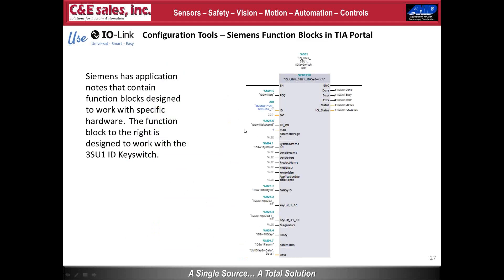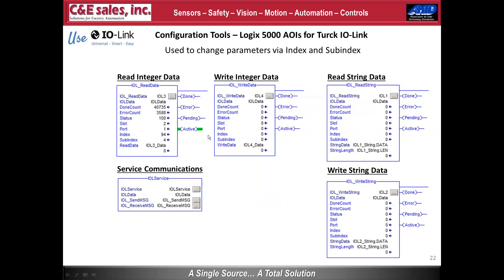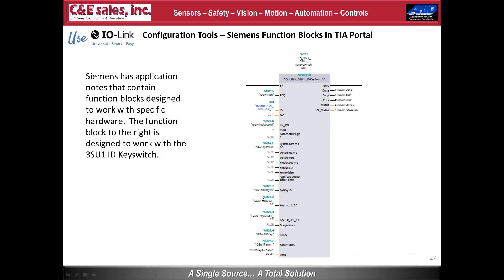Here's an example of the Siemens IO-Link device block interfacing with a Siemens Sirius ID key switch. The ID key switch uses keys with unique hex codes and authorization levels for machine or HMI access. Using the read and write parameter block, you can read out the 10-hex-digit key ID to identify operators and control machine access based on that ID. Siemens uses one block versus TURK's couple of blocks for reading and writing parameters.